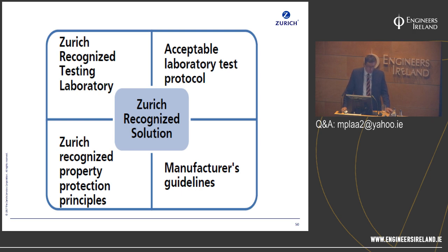Sorry, Gary, what is typically seen as the maximum compartment size that a water mist system can manage, or is there such a thing? There will be limitations on that. When a manufacturer goes to a test lab, they determine, in conjunction with the test lab, the size of the space in terms of the square meterage, and also four key parameters: the fire load within that space, the volume of the space, the ceiling height, and also the pass-fail criteria. But the first three are really what you're looking at.